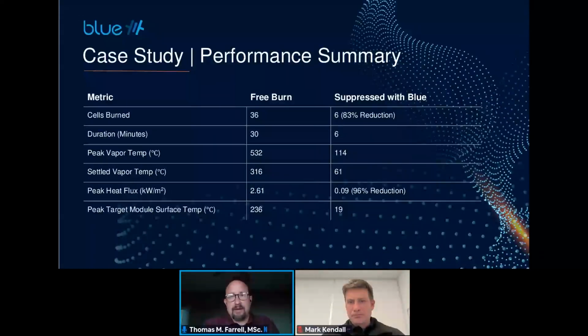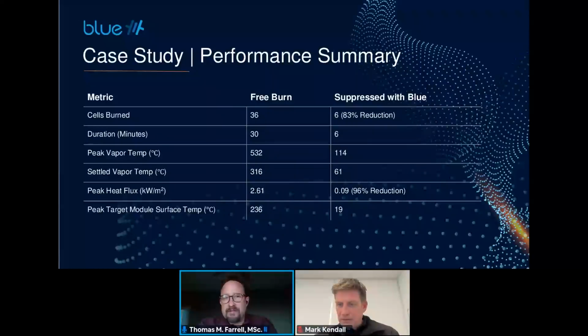So if we look at this in aggregate, the way it worked, the free burn versus the suppression, here's a table that shows that. We're looking at over an 80% reduction in the number of cells burned, which directly correlates to the gases that are generated and released. That directly correlates to the amount of toxic gases that are released. And that doesn't even include the reduction in toxic gases because of blue's ability to neutralize, or because of particulate matter being captured by this particular liquid.